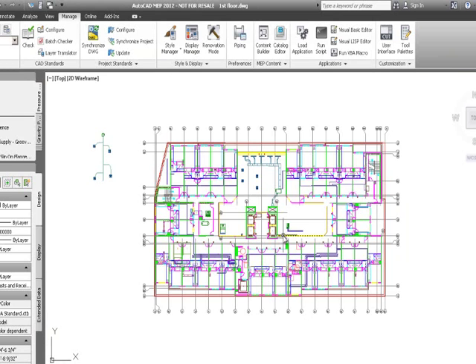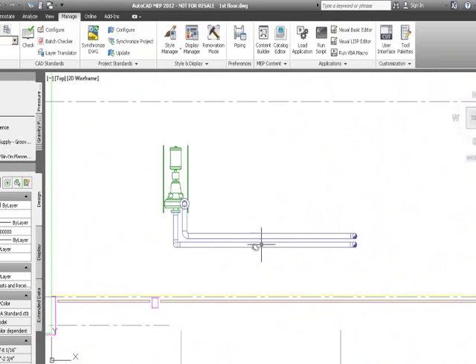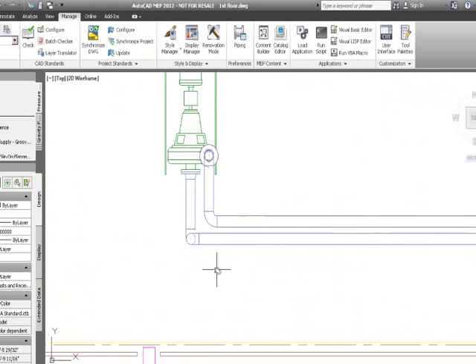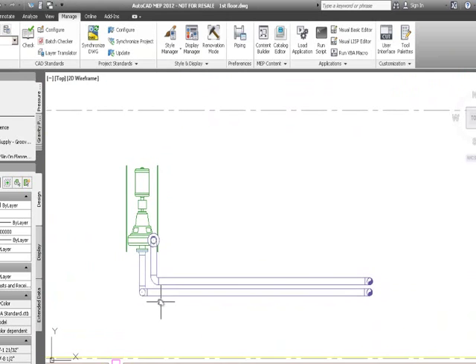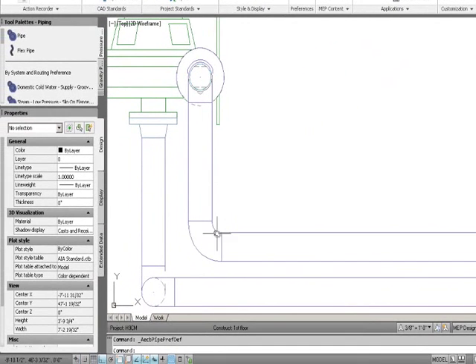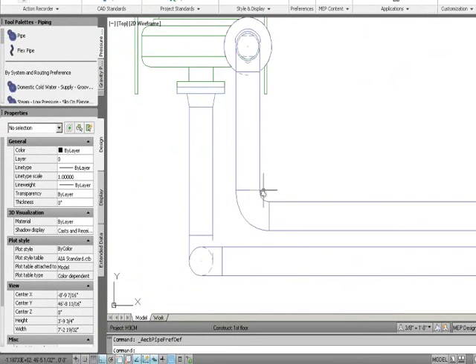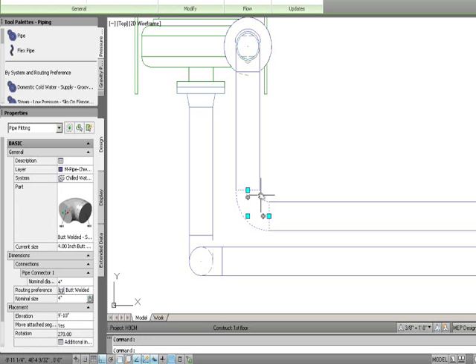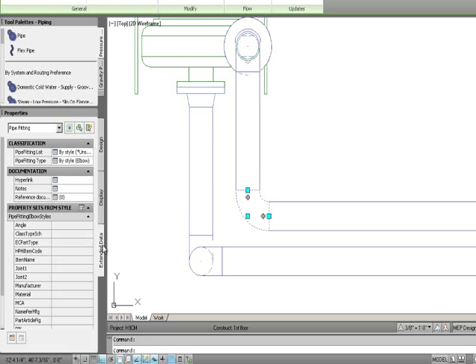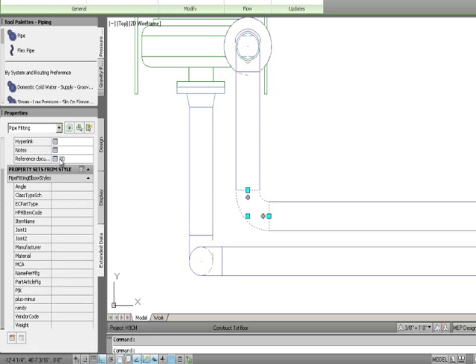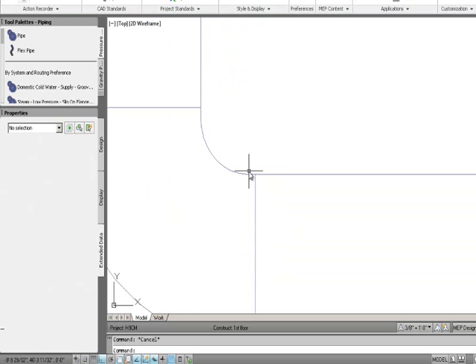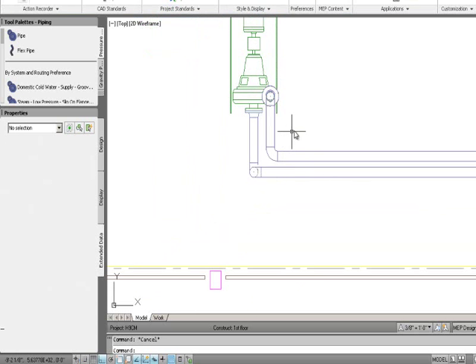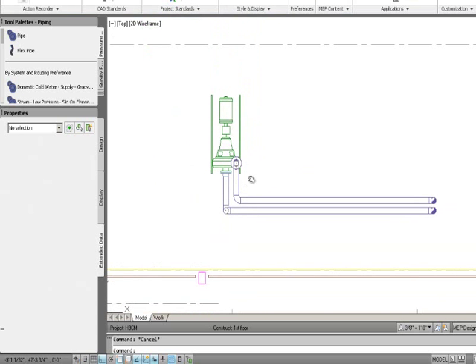Now let's talk about some differences when drawing. This system was drawn with out-of-the-box generic AutoCAD MEP content. When I click on an object and hover over it, you can see it's just a four-inch short radius elbow. Looking at the extended data, it knows really nothing about those parts — there's no weld gap between the elbow and the pipe, so it's just a straight-up butt-weld joint.